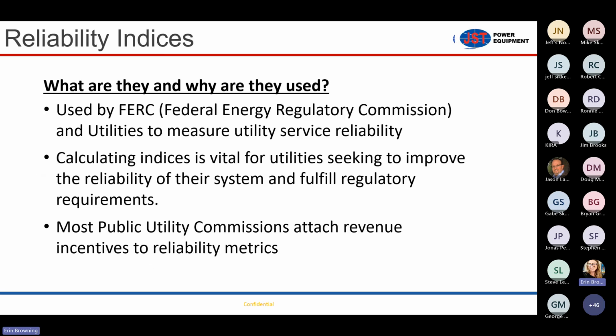The other application and value proposition that we have is definitely on utility safety and reliability indices. We talked about reclosers in the beginning that are out on the line. Reclosers have evolved to the point where they can do single phase trip, single phase close, three phase trip, three phase close, single phase trip, three-phase lockout. There are all the different configurations out there, but the overall intention of the recloser is to basically distinguish between momentary and permanent faults.